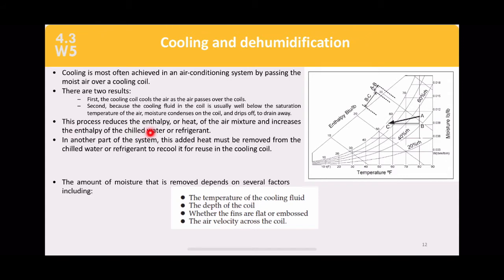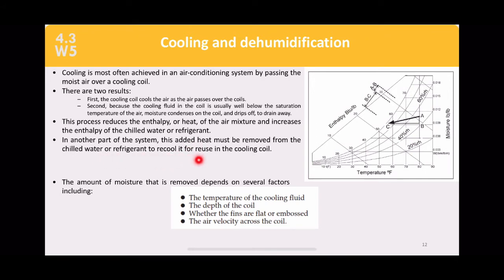This process reduces the enthalpy and temperature of the air mixture, while increasing the enthalpy of the chilled water or refrigerant. In another part of the system, this added heat must be removed from the refrigerant — you have an evaporator inside the room and a condenser outside. This is the refrigeration cycle. The amount of moisture removed depends on the cooling fluid temperature.